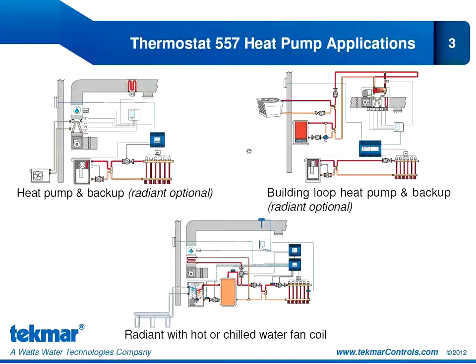Our second heat pump application shows a building loop. So this is a closed water building loop where individual units in the building are equipped with water-to-air heat pumps. We've also shown the option of adding the radiant flooring to this system. If we do, our radiant is 1st stage heat. Our heat pump can provide a 2nd and a 3rd stage of heat, and again we can provide a 4th stage of heat with the electric strip backup. In cooling mode, our heat pump could provide up to 2 stages of cooling. So this is again a 4-stage heat, 2-stage cool heat pump application.